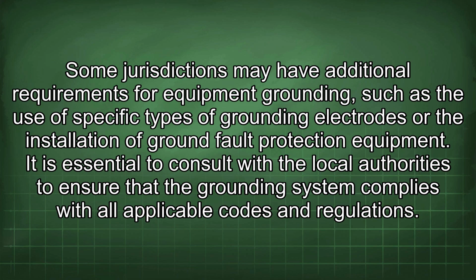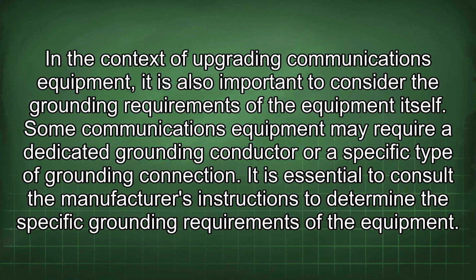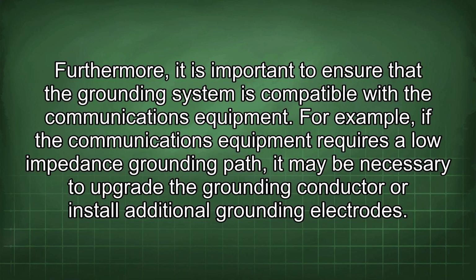In the context of upgrading communications equipment, it is also important to consider the grounding requirements of the equipment itself. Some communications equipment may require a dedicated grounding conductor or a specific type of grounding connection. It is essential to consult the manufacturer's instructions to determine the specific grounding requirements of the equipment. Furthermore, it is important to ensure that the grounding system is compatible with the communications equipment. For example, if the communications equipment requires a low impedance grounding path, it may be necessary to upgrade the grounding conductor or install additional grounding electrodes.